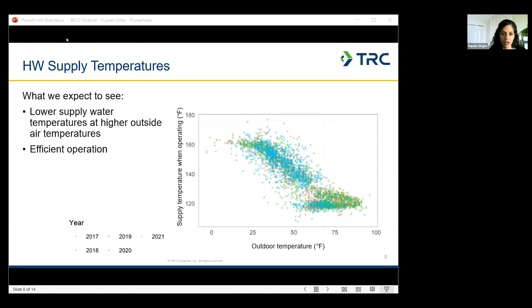So what I'm showing here is a system that's very well controlled. Out of all the 259 buildings in our data set, only about a quarter of them showed any sort of consistent correlation between the supply water temperature and the outdoor air temperature. Most buildings, meaning the other 3/4 of the buildings, generally had very poor control over the hot water supply temperature. So I'm just going to give a snapshot, just a few examples of what some of those other buildings looked like.